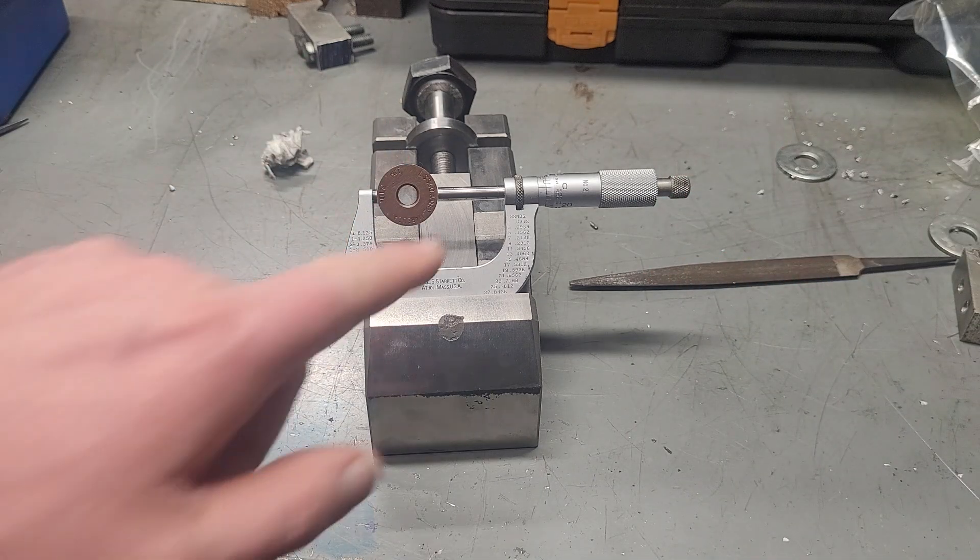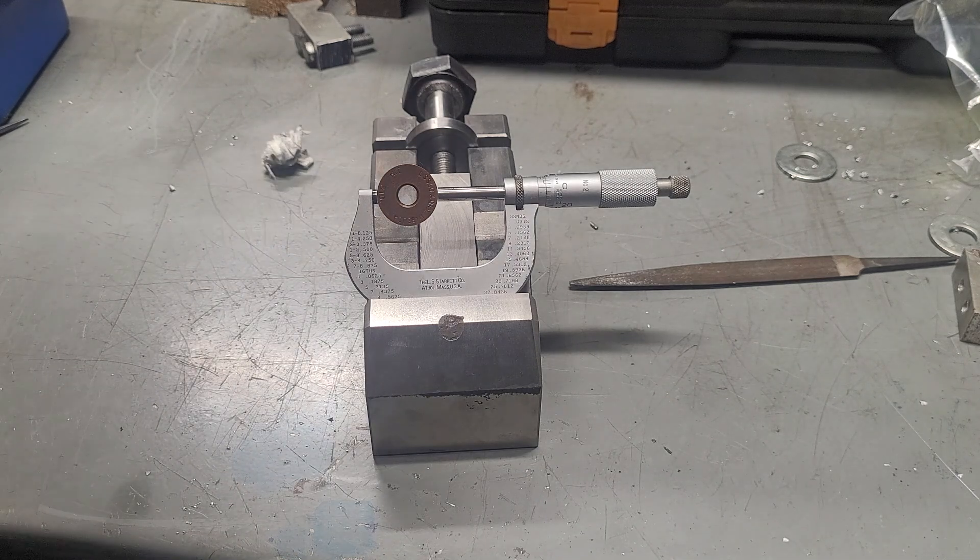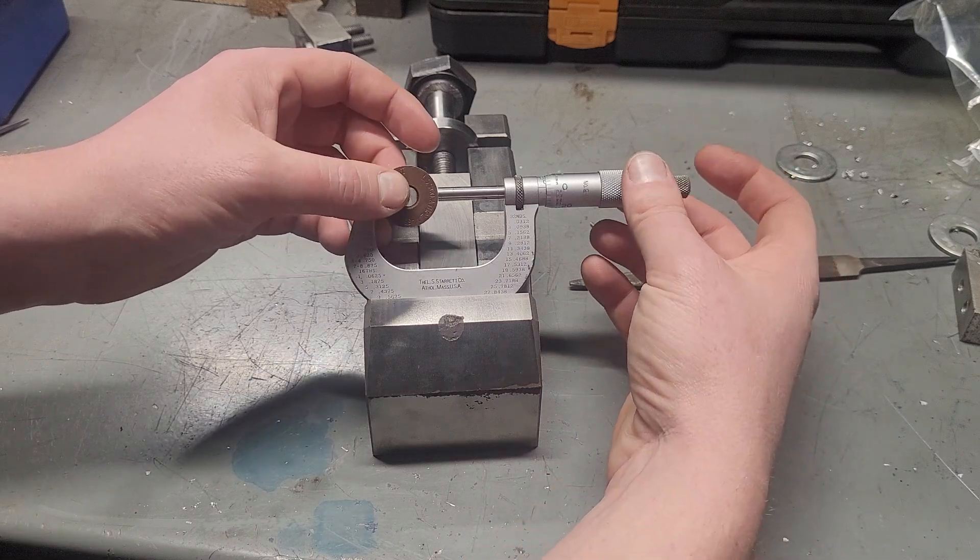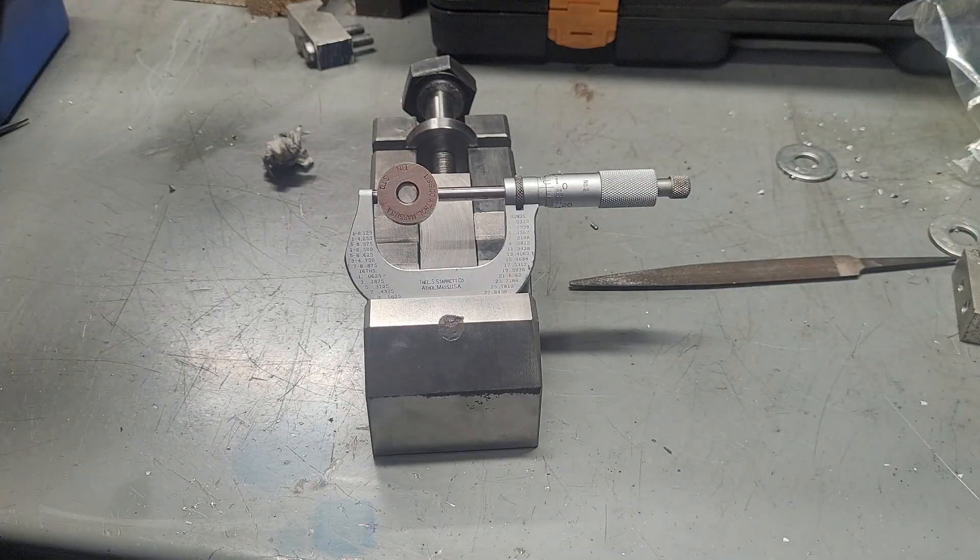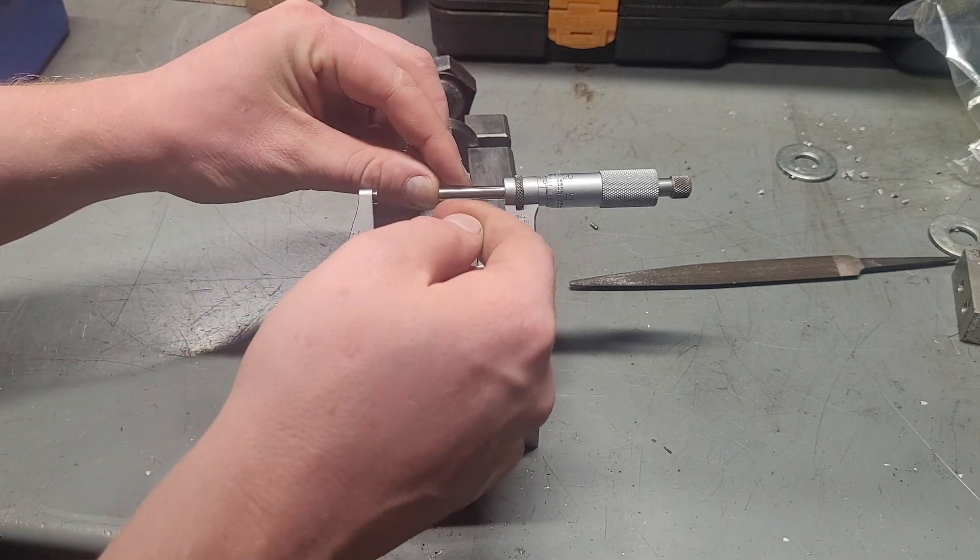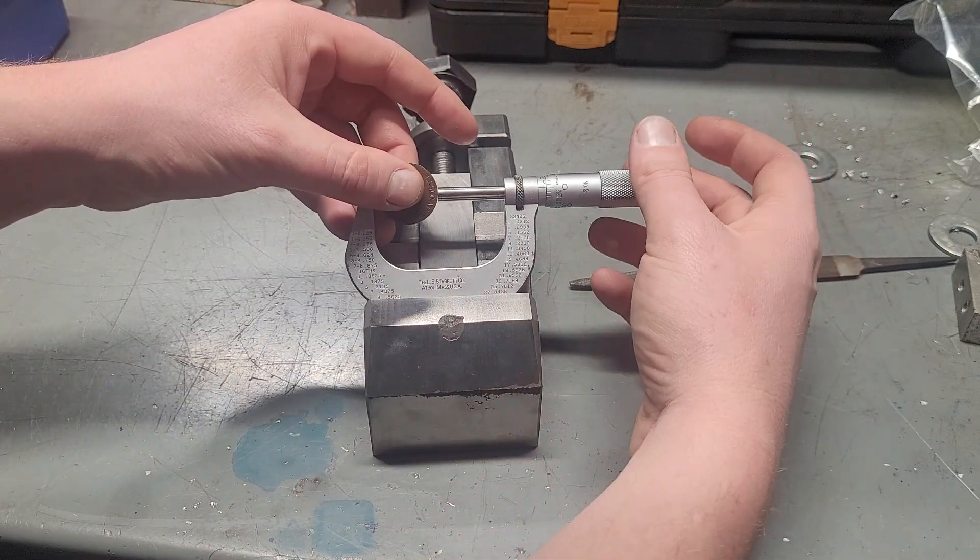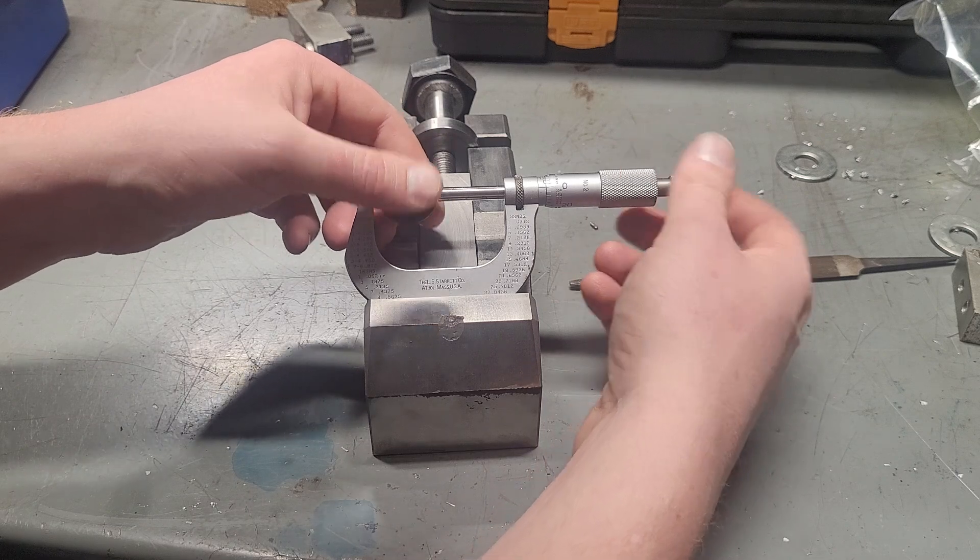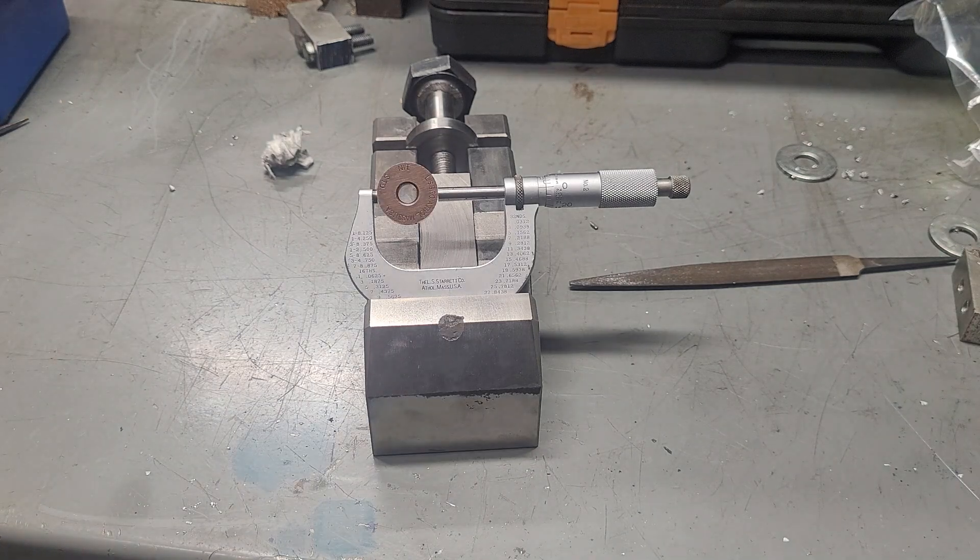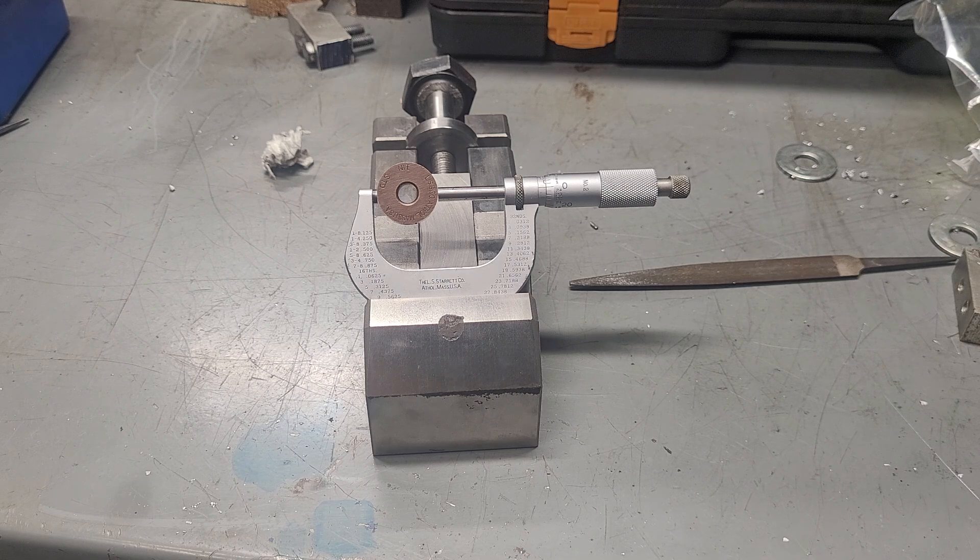So right here, we can see on the line on the vernier scale, we're reading one ten thousandths of an inch off, which is actually not really that big a deal from my accuracy standards. And we're pretty repeatable on this. Now, does that mean we need to recalibrate? No, because all that means is I am going to wipe the anvils off and try again. And guess what, guys? We're reading a tiny bit smaller. So I just did this again and we're dead on zero. So what we just demonstrated here is a limit of repeatability to a measuring instrument.